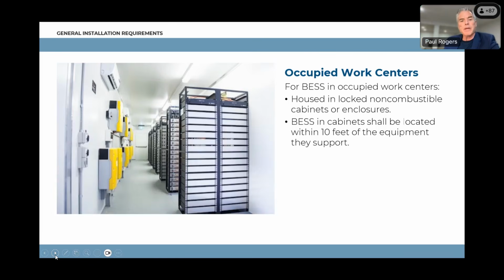Occupied work centers—here's a good picture here. What we've seen is they need to be in locked, non-combustible cabinets or enclosures, and we're seeing a lot of these more on the lead acid side for battery energy storage systems. That doesn't mean they can't have lithium ion, but if they do, they need to have gone through testing and have their required 9540 listing, and any system meeting both thresholds in the code needs that 9540A listing. So really take a look at this when getting into occupied work centers, and it should be within 10 feet of the equipment it's supporting—that's in the code, just FYI.